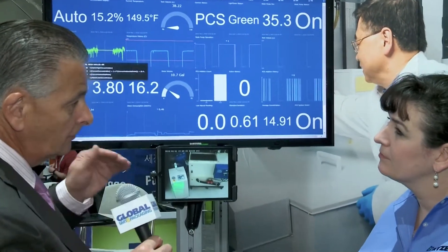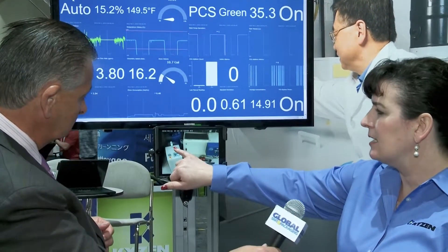How does the alarm system work? Is it a traffic light system? It is. The PCS has a light tower with a green light, yellow light, and red light. In addition to that physical alarm, you have an audible alarm. And then the system has the intelligence to set up an automated text message or email to whoever is responsible for that cleaning process. So rather than running 1,000 boards over the next hour before it gets acknowledged and resolved, the engineer responsible for this process can immediately take care of it and make sure you're within your cleaning specifications. It can go to a tablet, watch, iPhone, Android phone — as long as you have it. The software dwells in the cloud itself.